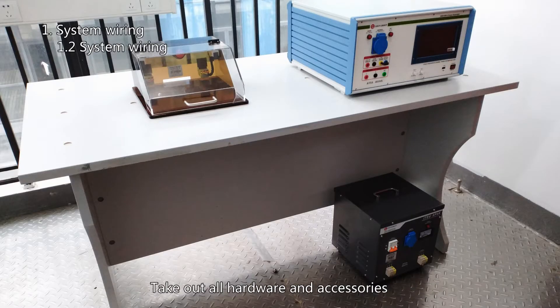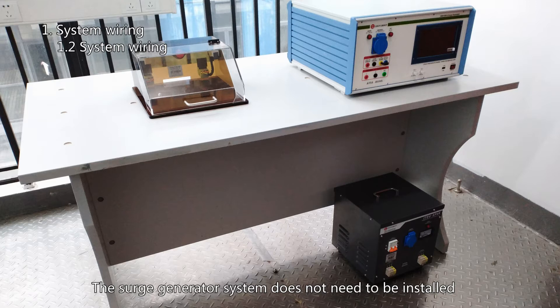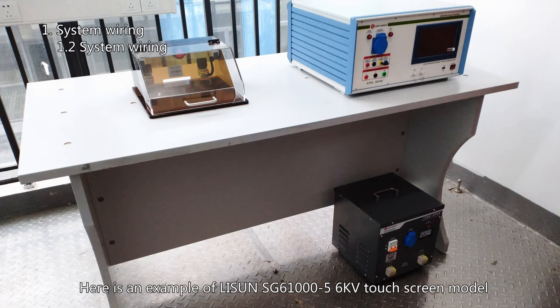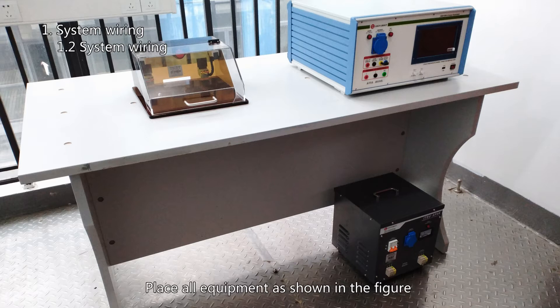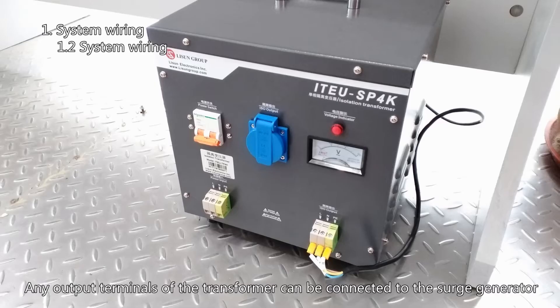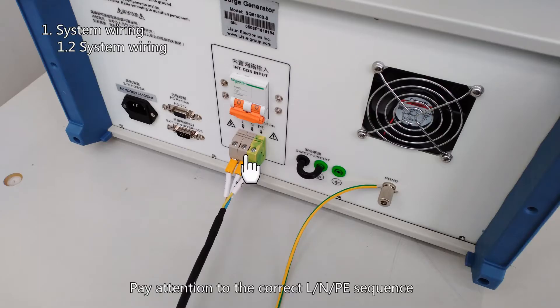Take out all hardware and accessories. The surge generator system does not need to be installed — only wire connection is needed. The method of using surge generators with different voltage outputs is the same. Here is an example of the LISUN SG61000-5 6KV touch screen model. Place all equipment as shown in the figure. Connect the ground line for the surge generator. Any output terminals of the transformer can be connected to the surge generator. Pay attention to the correct L, N, PE sequence.